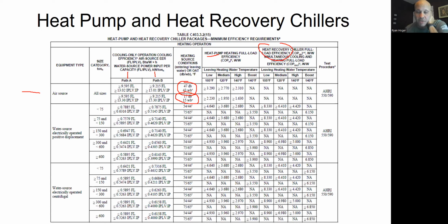more efficient. If it's an existing building and you're trying to meet the old demands where the building was designed for 180-degree heating water, then you're probably going to go ahead and design the building for 140, right? Because that's probably about the most you can get out of a heat pump. And that's the way it's going to go. If it's new construction and you could design the whole thing for 120, great. And if it's like radiant flooring systems, then you'll design the whole thing for 105. That's why you have these 3 numbers here.